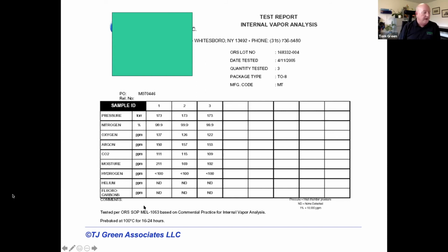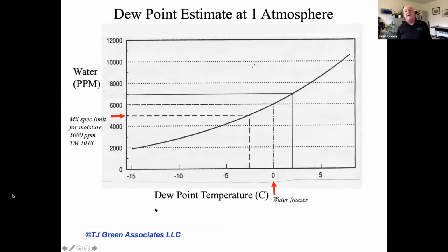But this was actually done to a commercial spec. So if you've got a battery in your pacer or in your device, you're going to have to be careful at what temperature you do the RGA. That's something that can be accommodated, but you're not necessarily in full compliance with the method. That's kind of how people do it.